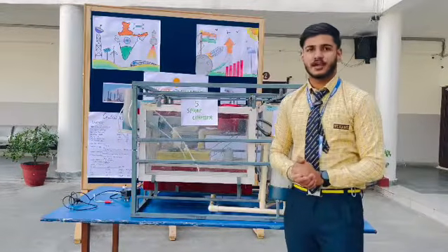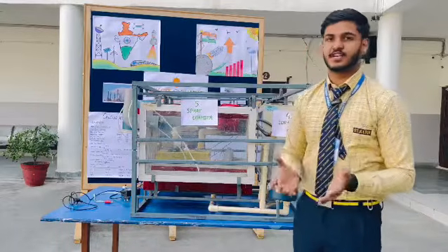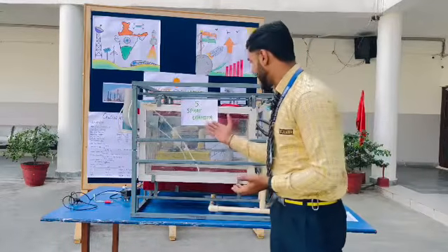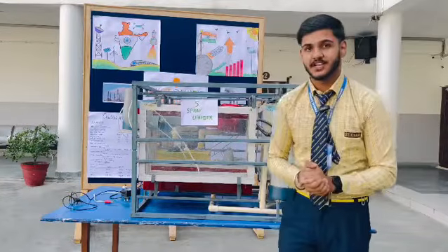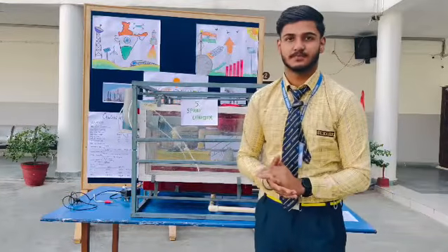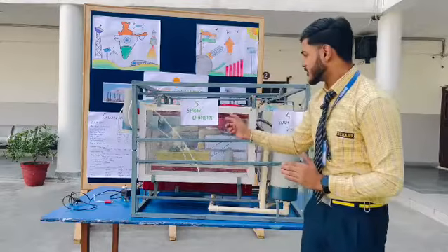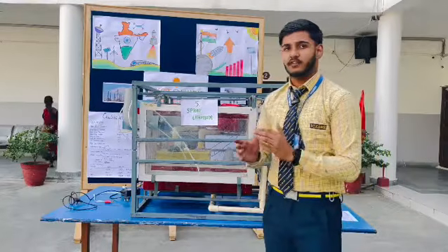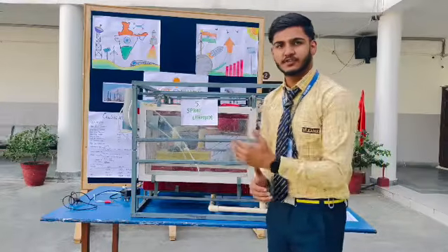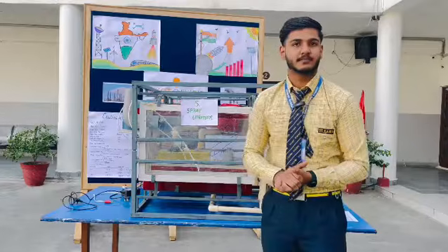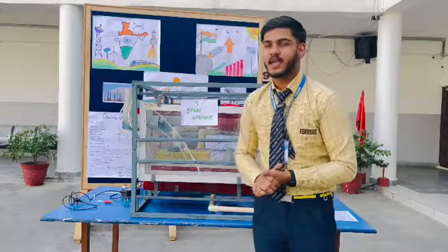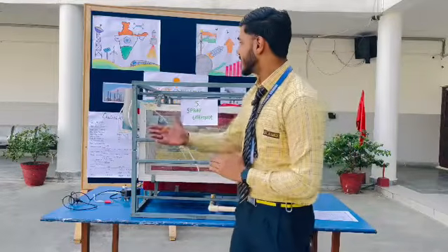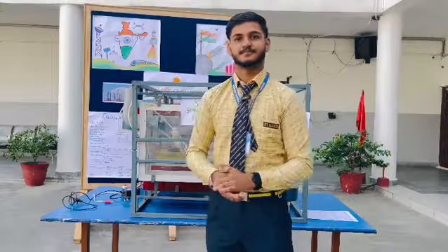The next section is the spray chamber and the slurry box. We use a limestone and gypsum mixture which is basic in nature. The exhaust gases entering this chamber are already free from the solid particles but still contain some acidic gases. When we spray the basic solution in this chamber, it reacts with these gases and reduces and eliminates the acidic effect. Excessive carbon dioxide gets absorbed in the solution. As a result, clean and safe air will be released into the environment.